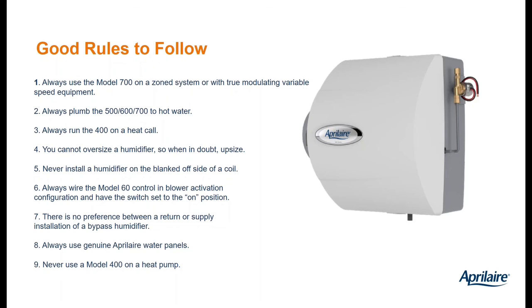because you have those small reservoirs that are going to fill, and that's going to allow that water to typically cool to room temperature. So you don't get BTUs from the air, you don't get BTUs from the water, you're going to get a lot less evaporation. And so we just don't want consumers to experience lack of humidity. Now there's lots of heat pumps out there that run enough, right? Heat pumps usually run longer, so you get longer run times, and so the duration of the calls for humidity make up for the lack of evaporation over every minute it runs. So you wind up with enough gallons per day to properly raise the humidity of the house.